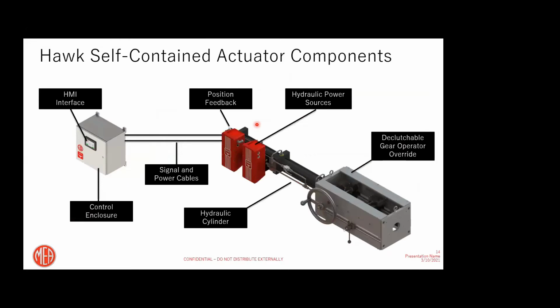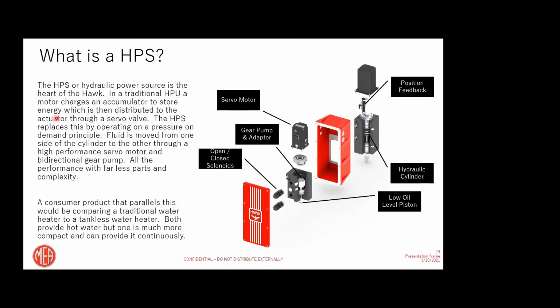These are the components of our self-contained electrohydraulic actuator. You still have your gearing mechanism, and then you have your hydraulic cylinder with the position feedback, which can go on the cylinder or on either side of the mechanical override. Then you have your hydraulic power source, and additionally you have signal and power cables connected to your control enclosure with the HMI interface. Basically, this unit works by utilizing a servo motor coupled to a gear pump. The beauty of these servo motors is that they are industrial servo motors used in a lot of automation all around the world and have been used for many, many years. And now we are just using them with a hydraulic gear pump.